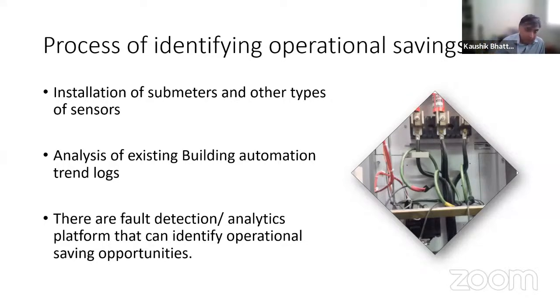During my work in India, I was doing a lot of energy audits for different industrial plants. There was a lot of confusion in terms of, if I give you an energy meter, where will I connect it, which cables do I need to put in. It's a star delta system. Not sure if you're familiar with star delta starting, but the ability to implement or install these meters correctly and capture the right energy and power is very important.